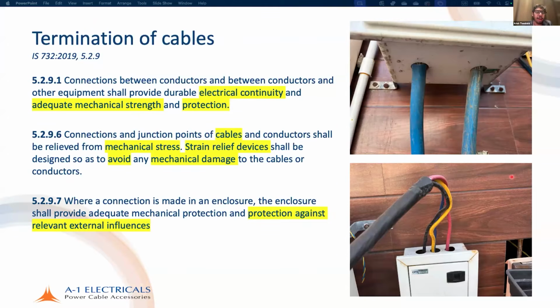Connections and junction points of cables and conductors shall be relieved from mechanical stress. I'm repeating: it's not only the connections and the junction points that have to be made correctly, they have to be relieved from stress as well, because any stress on the cable will end up providing stress on the terminations. That's why we saw earlier that glands provide strain relief.